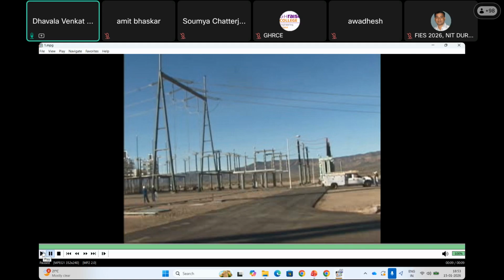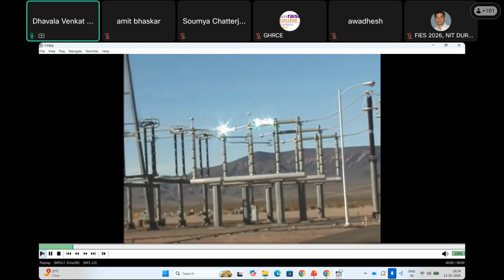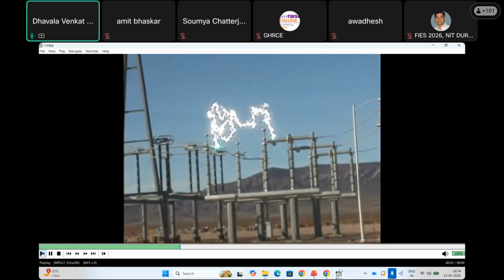Once again, this is the opening of the isolator. It is an isolator, which cannot be operated under load condition - it can be operated only under offload condition. Even under offload condition the spark is somehow present, but when it is coming close to contact or opening from the contact, horning of the contacts is very important, as we know. From the operation point of view, let me just open the contacts - see, this much of it.